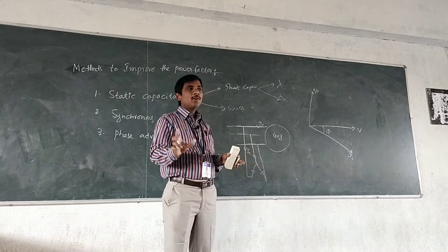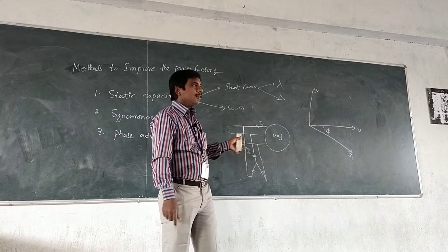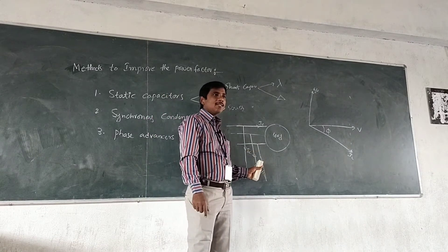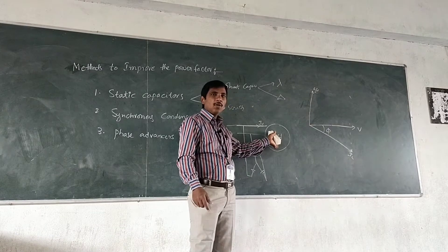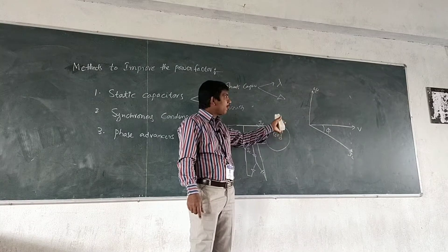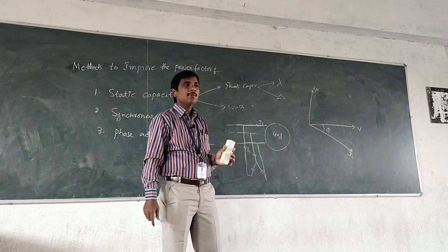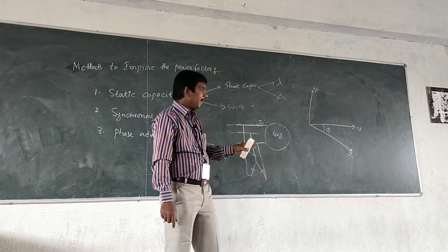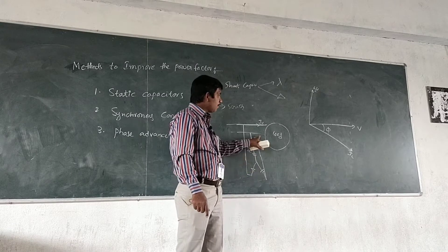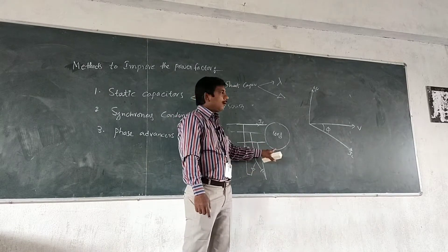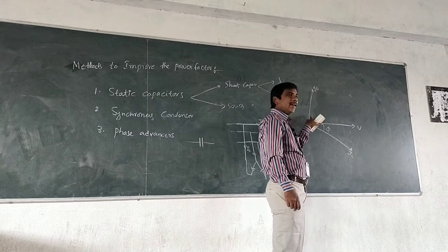In the case of an induction motor in the lab — if the induction motor is not connected with capacitors, it takes the lagging component of load current. Hence the load reactive power must come from somewhere. If you connect capacitors, they will give the reactive power required for the load. This is the capacitor characteristic which supplies leading reactive energy.